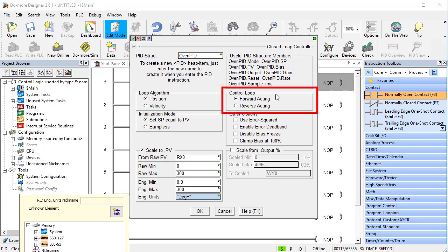This is a forward acting process. That is, if we increase the output, the temperature increases. A reverse acting process would be like a cooling system, where as our control output increases, the process temperature decreases. PID needs to know that to get the math to work out.